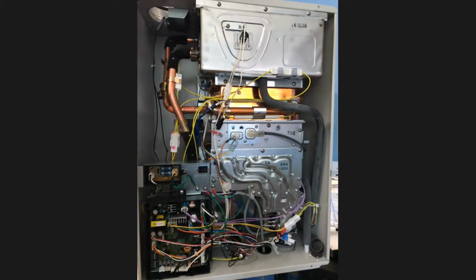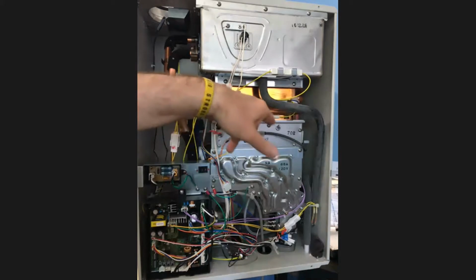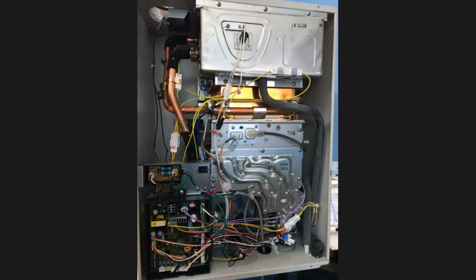When we get into gas supply pressures, 8 inches is the minimum on propane, 4 inches the minimum on natural gas. On natural gas, 10.5 inches of water column is going to be our maximum, but 14 inches will be our maximum on propane. And the propane conversion is a bunch of little orifices that go into the burners to make that adjustment. So while it looks busy in here, if we were actually pulling this whole thing apart, it's about 20 minutes and I could have everything out of the entire cabinet. There's not much to it.